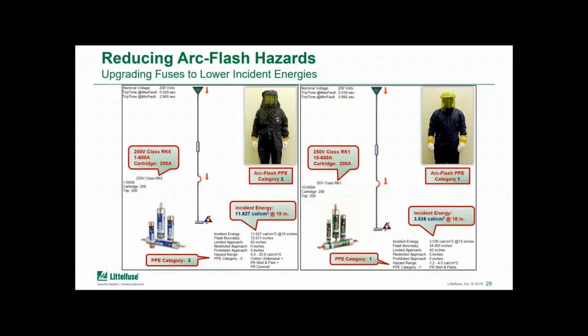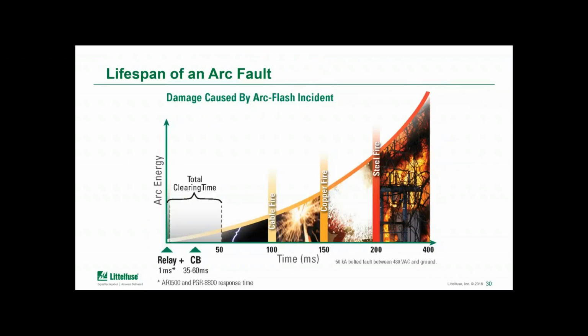So that's something that can have a significant impact, and that might even be in line with what the daily wear of that worker is out on the plant floor. So they may not even need to change PPE. As we already discussed, the energy released by an arc fault is a function of time, and the longer it persists, the more energy is released. As a real life example, think of a candle burning: if you move your finger over the flame quickly versus more slowly, you can feel that heat energy building up.